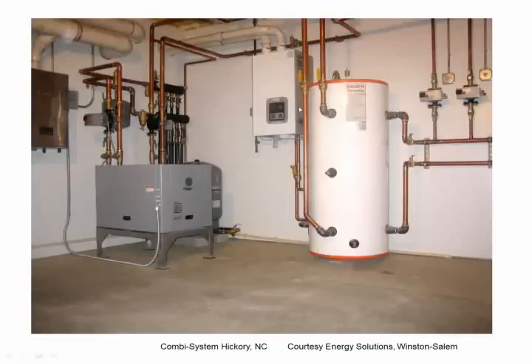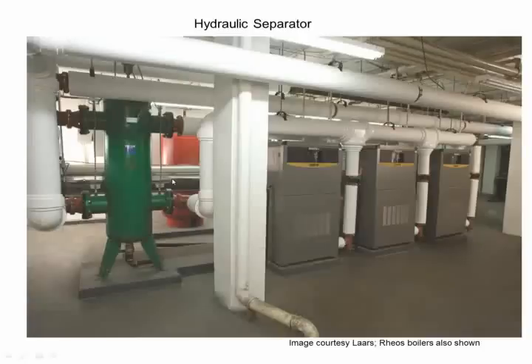A hydraulic separation, or a buffer tank used to hydraulically separate, is done here in this shot. So here's a buffer tank, and we have 4 ports, 1, 2. This is our secondary side, a bunch of pumps sending heat. And perhaps this is a heat pump system, perhaps chilled water up to our system. And connected to our buffer tank, our heat pump, is our primary side. So we don't have any interference on our primary pump. This is a Caleffi buffer tank, which has also the added feature of additional ports on the side, enabling a combination system. So this contractor, in fact, they'll be on board with us, I think, on our next webinar talking about this system, Prestige boiler as backup in those cold winter months when they need added heat versus what the heat pump can do efficiently.